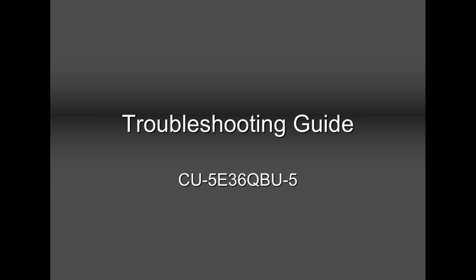Now, if you noticed, I didn't speak about any troubleshooting on the single zone, because the troubleshooting error codes for a single and a multi-zone are the same. And if you look at the app, if you have the app, you will see all the error codes there apply for both single and multi. There are a few error codes like the F17, which is freezing of an indoor unit during standby mode, and H36, cross wiring. These two error codes are very popular when somebody has crossed the wire, and that somebody is none other than the installer.